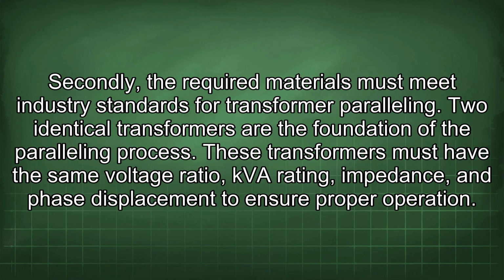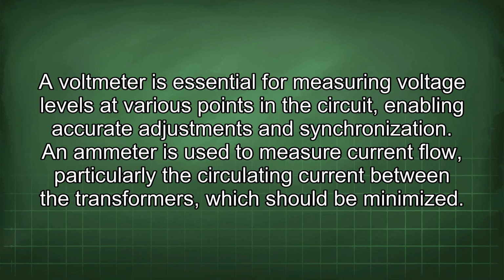Secondly, the required materials must meet industry standards for transformer paralleling. Two identical transformers are the foundation of the paralleling process. These transformers must have the same voltage ratio, kVA rating, impedance, and phase displacement to ensure proper operation. A voltmeter is essential for measuring voltage levels at various points in the circuit, enabling accurate adjustments and synchronization. An ammeter is used to measure current flow, particularly the circulating current between the transformers, which should be minimized.